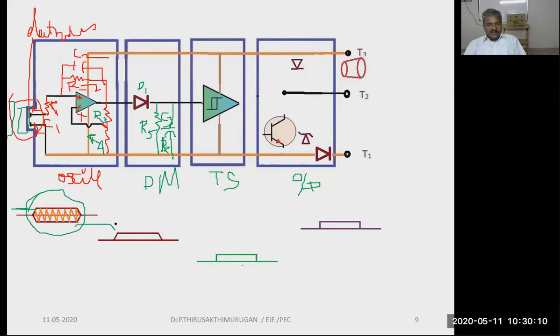So when the object is nearing, the demodulator output starts increasing. As I told you earlier, when the demodulator output starts increasing, the input to the Schmitt trigger is also increasing. The Schmitt trigger goes to high voltage level. So the Schmitt trigger goes high. The demodulator output is increasing, and the Schmitt trigger output is also increasing. Since the object is nearing the sensor head, we should generate a positive output. So output should be high.